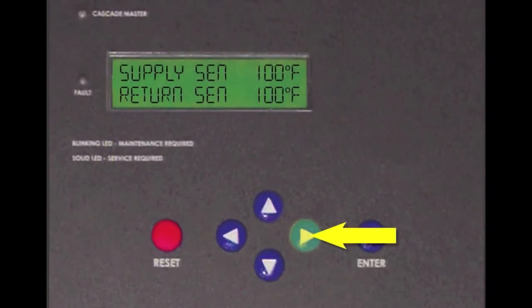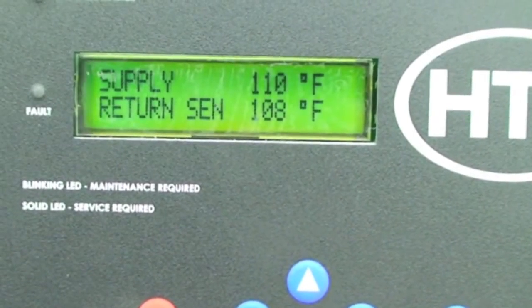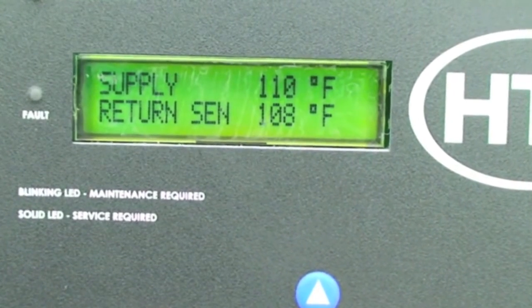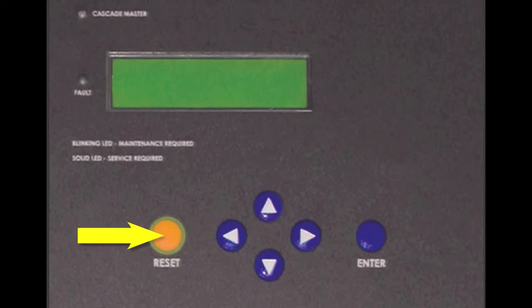You can further check the temperature by going into the status menu and see what the temperature is showing on the supply sensor. The boiler will not restart until this cause of excessive temperature is repaired and the reset button is pushed on the display.